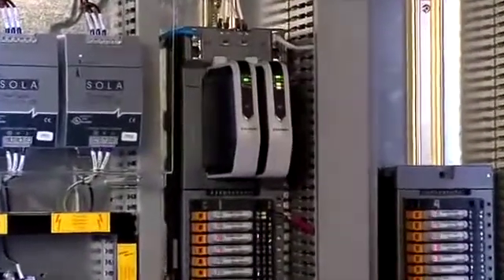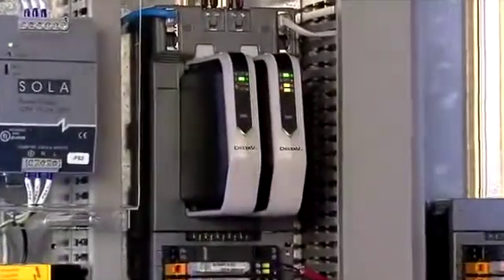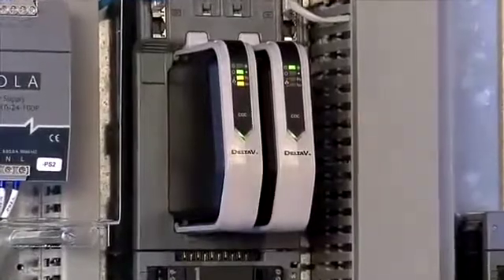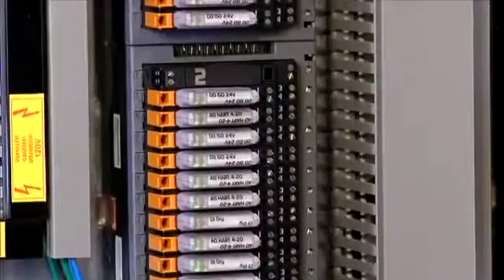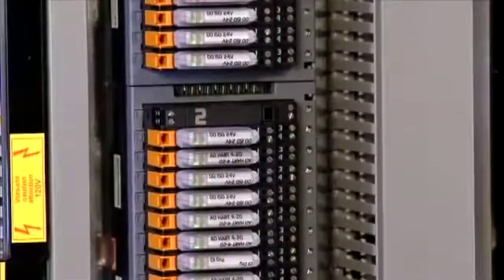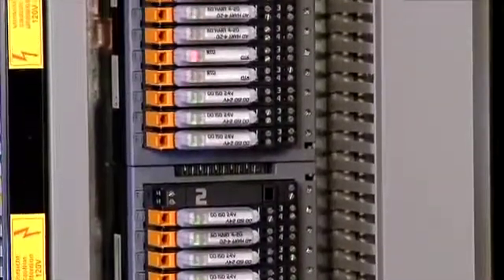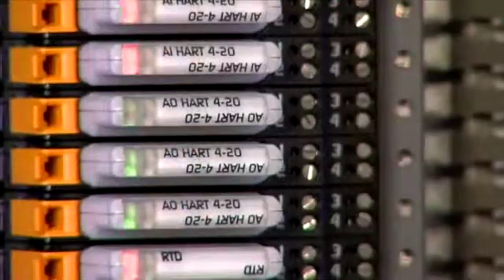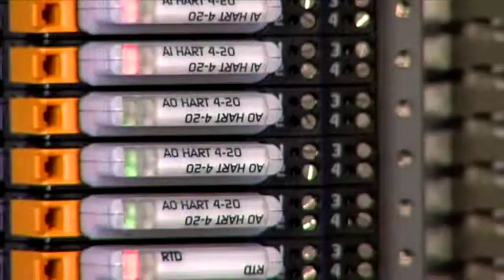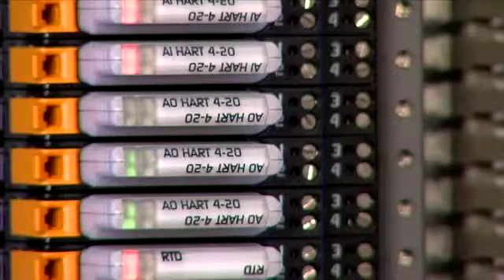Another important component is the CHARM I/O card, or CIOC, which supports up to 96 individually configurable channels, providing the redundant communications between the CHARMS and the Delta V S-series controllers on the control network.